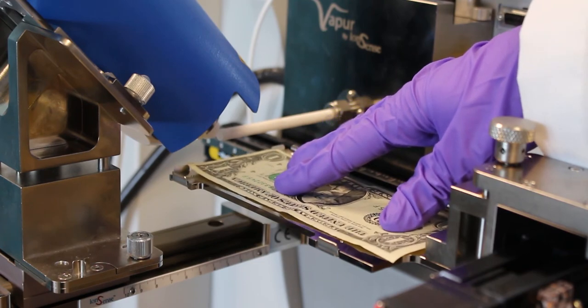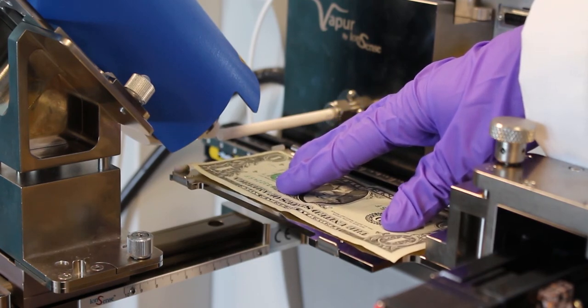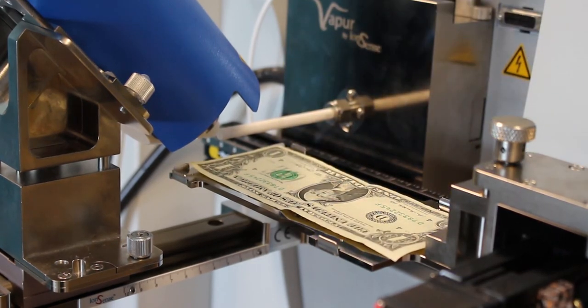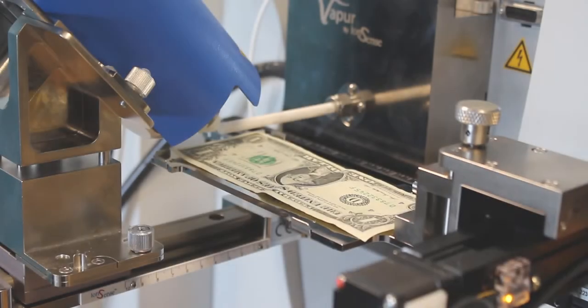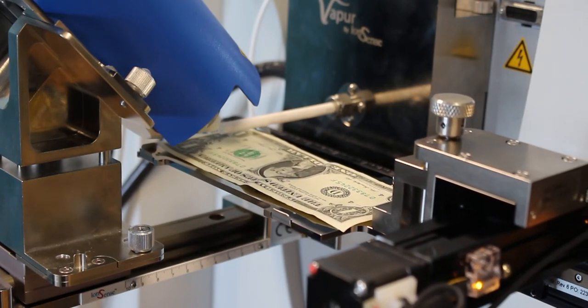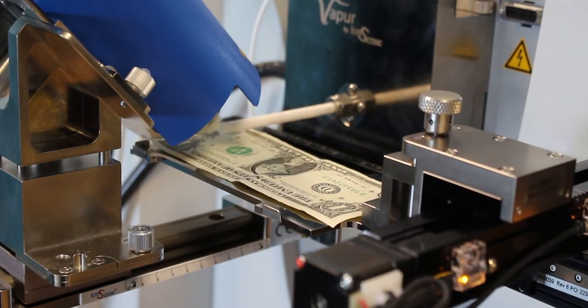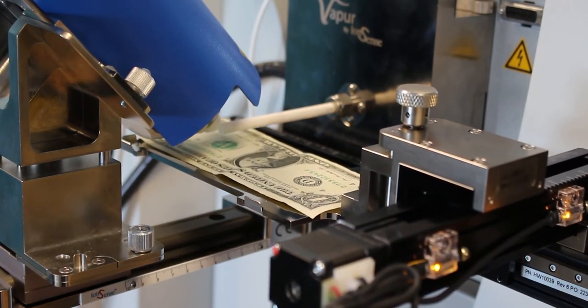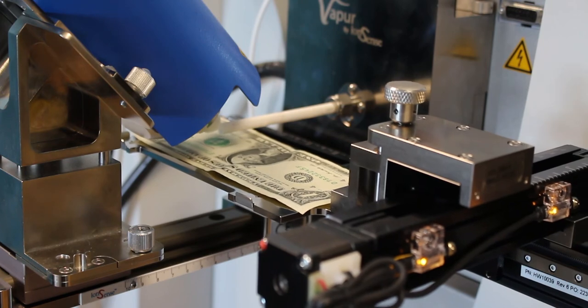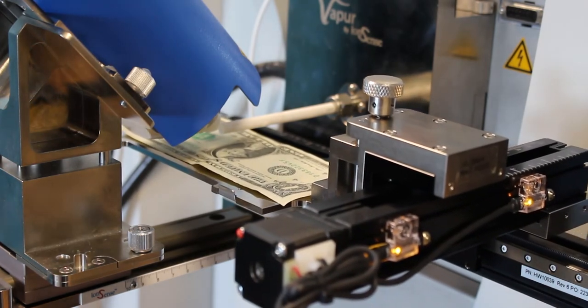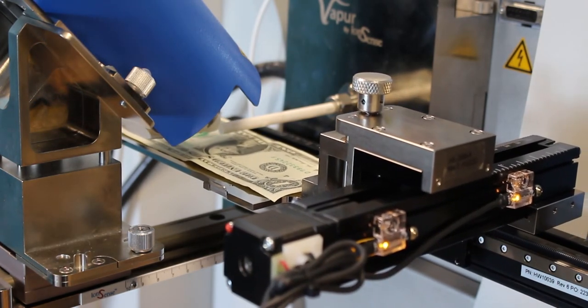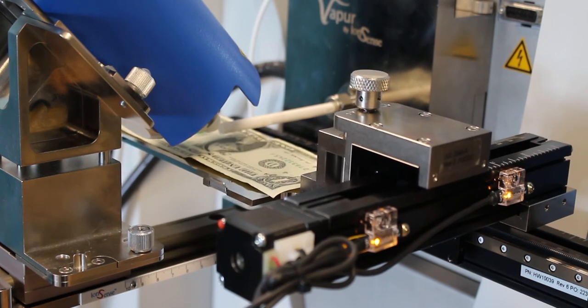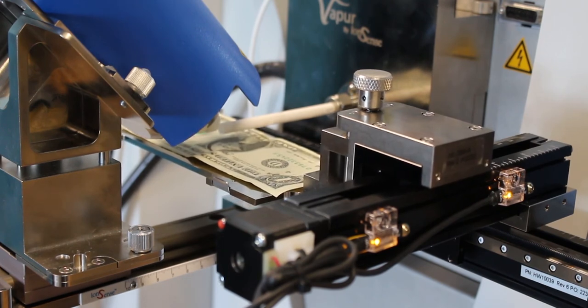In this setup, the sample is placed onto a plate attached to a linear rail. It's also attached to a second linear rail in the X direction, which allows for XY movement of the plate and scanning across the surface. The XY rail's positioning and speed can be automated or adjusted manually through the DART software.